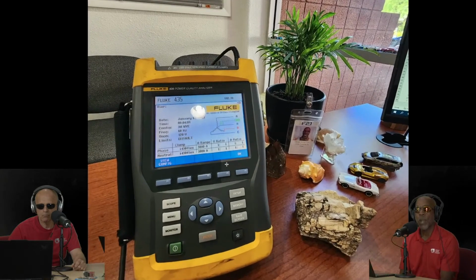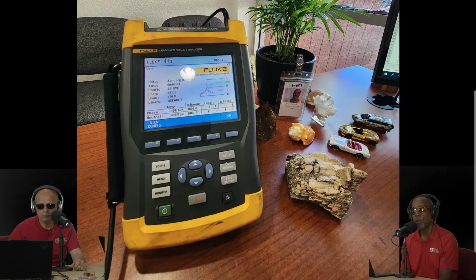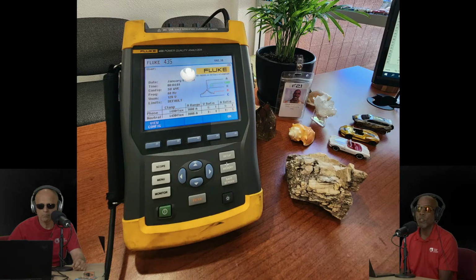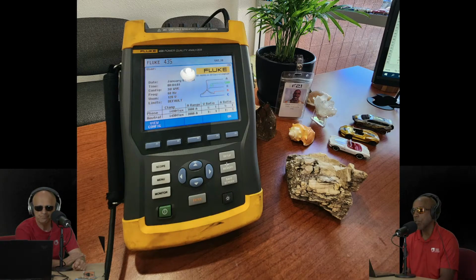And in your operation, you can just let it run. This meter will capture everything: the sine waves, the sags, the dips, whatever is coming into your power line, first to determine if you even have a power problem. And you can take this data and do proactive things with it in terms of protection, like Pete was mentioning. This is a device that will record voltage dips, swells, and transients. It puts an exact timestamp on when the event occurred. So it's really nice to do this proactively before you make any investment in what you might need.